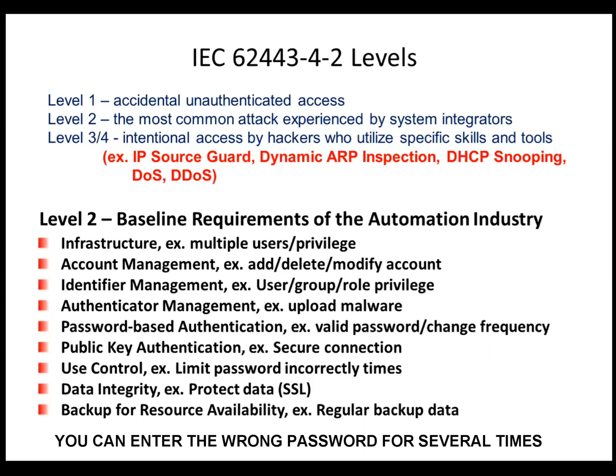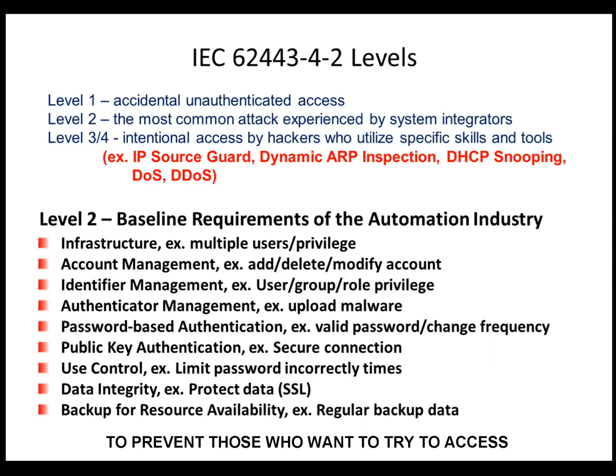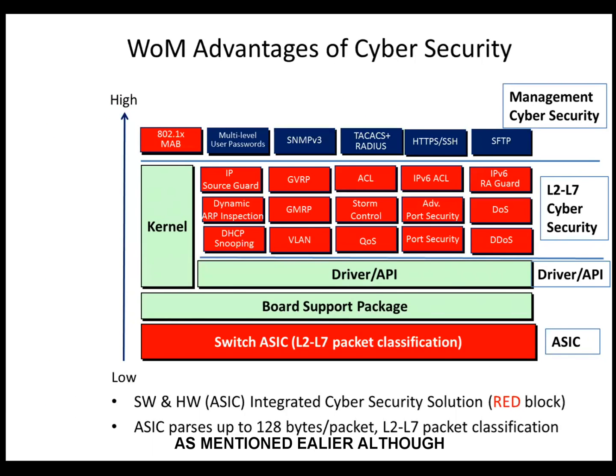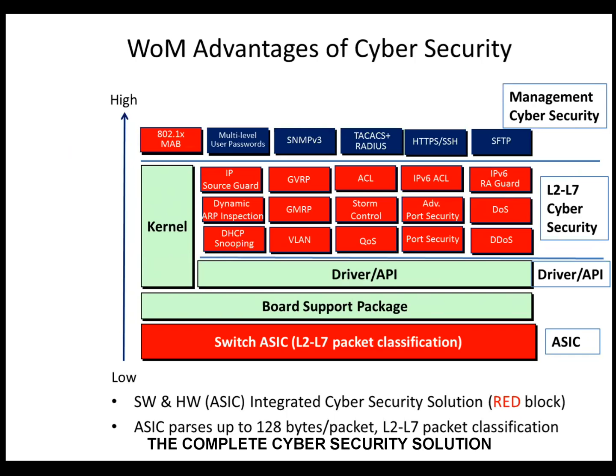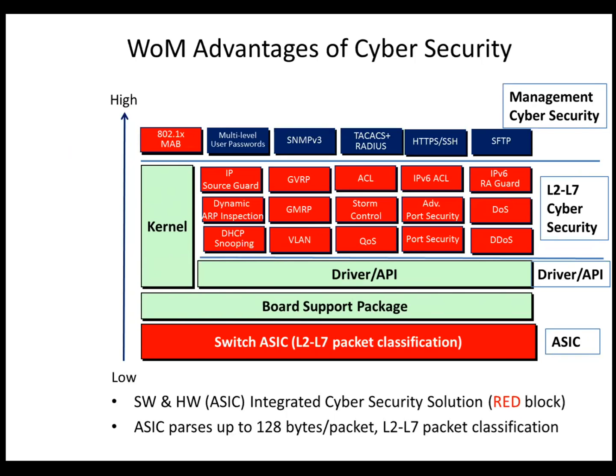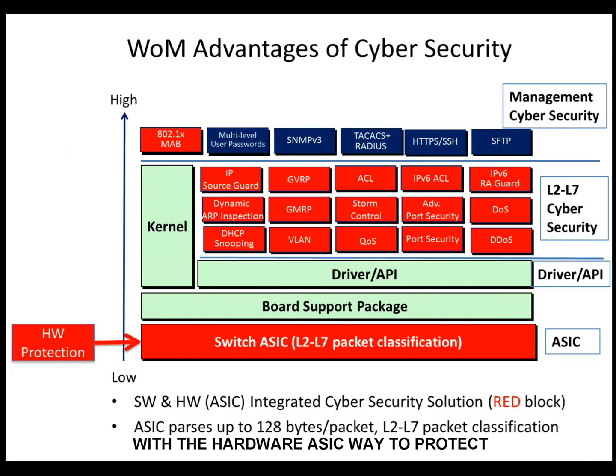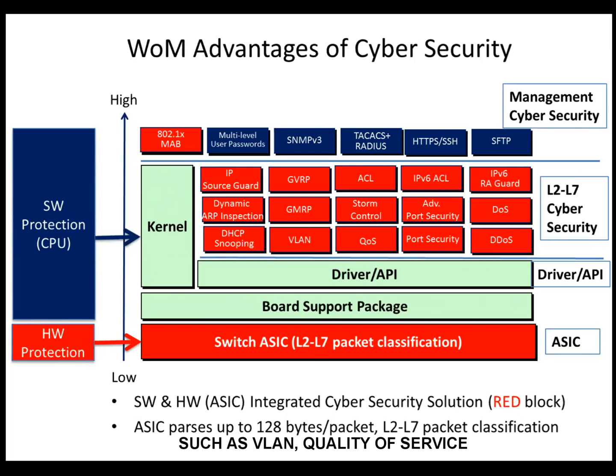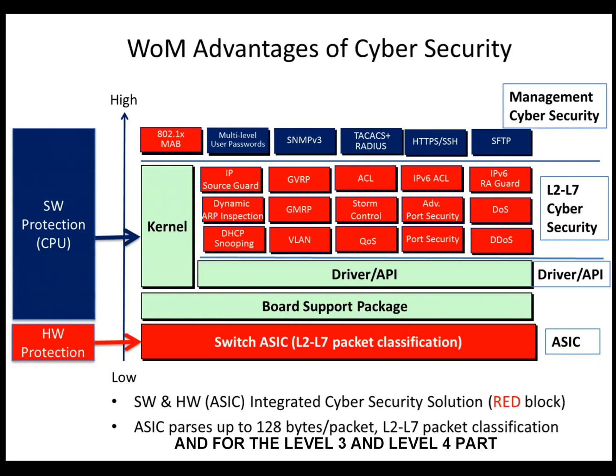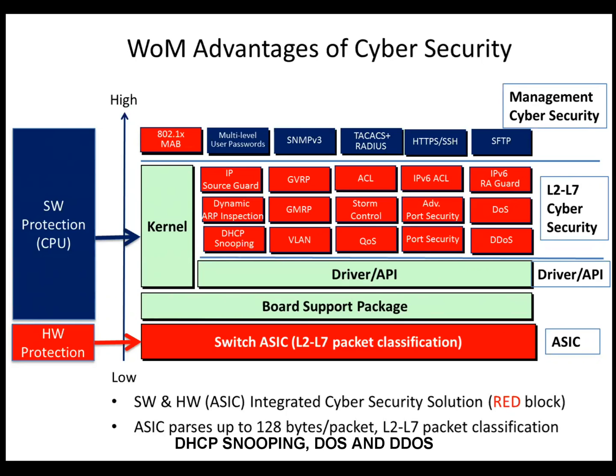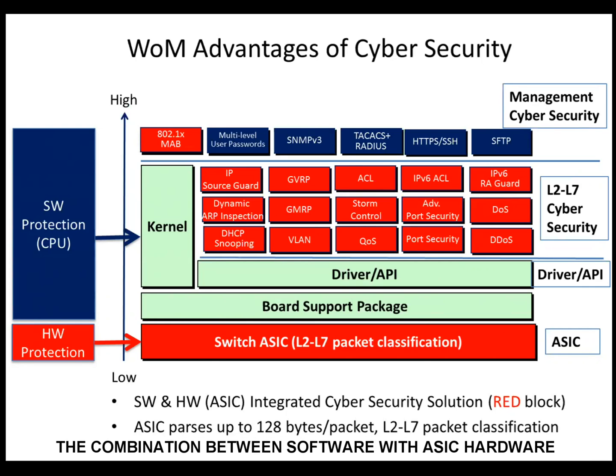For level 2, the larger brands in general industry emphasize support functions: user account management such as adding/deleting accounts and setting permissions, and access control — for example, locking out access after several incorrect password attempts. Although old equipment may achieve some cybersecurity protection through firmware upgrades, complete cybersecurity still requires both software and hardware. The red-marked parts use ASIC hardware protection, including VLAN, Quality of Service, and Port Security for level 2, and IP Source Guard, Dynamic ARP Inspection, DHCP Snooping, and DoS/DDoS protection for levels 3 and 4. The combination of software and ASIC hardware provides the most complete solution to prevent malicious attacks.